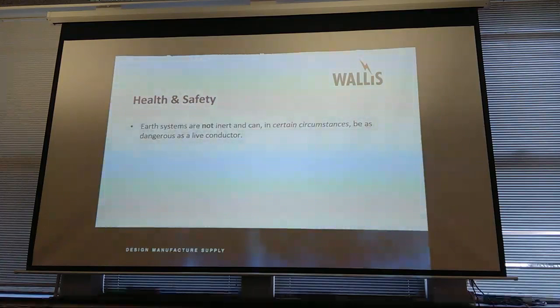Earthing systems are not inert. In certain circumstances, it's a dangerous live conductor. We've been to many sites recently, hospitals, data centres, places where there's a lot of electronics, a lot of drive motors, things like that. Put a clamp meter around the earth, and we've had in the region of 20 to 30 amps flowing down under steady state conditions. So if you go and disconnect that earth with one of these magic disconnect links that everybody likes, and you're bridging across that, it only takes 20, 30 milliamps to put the heart into fibrillation, and you've got 30 odd amps going through there.